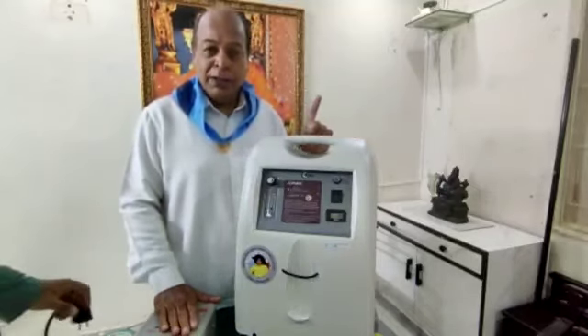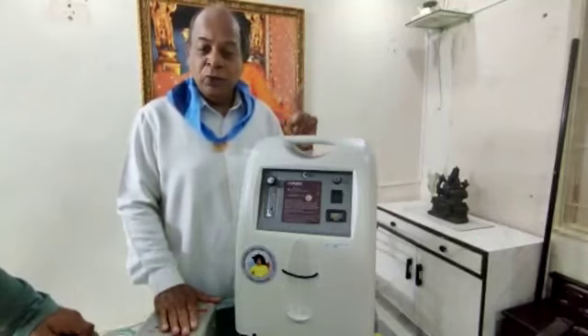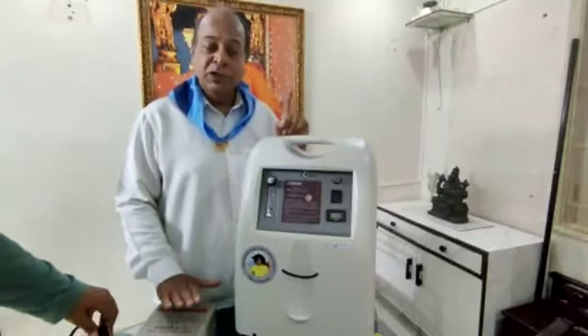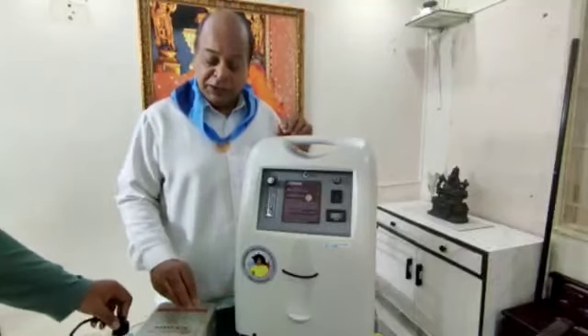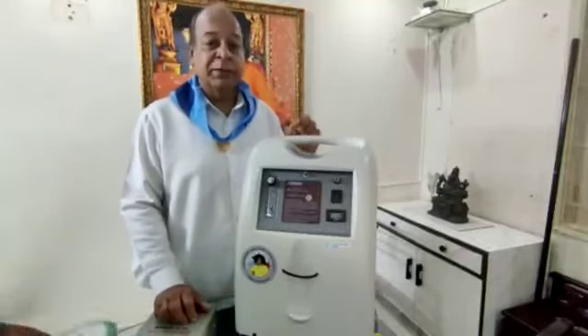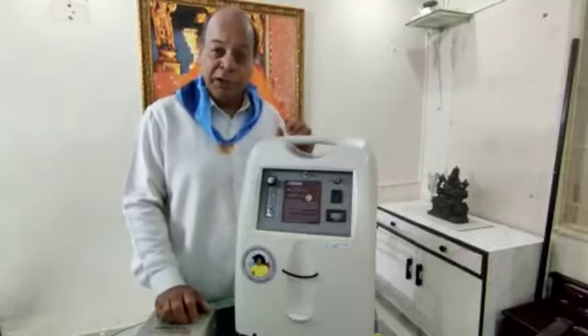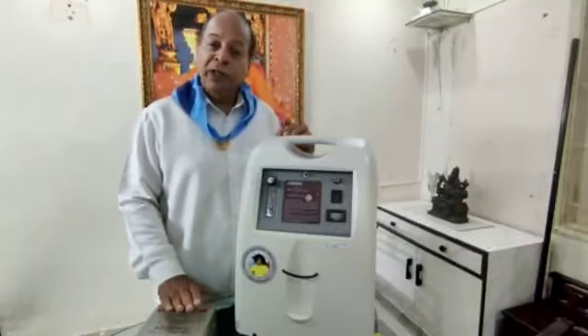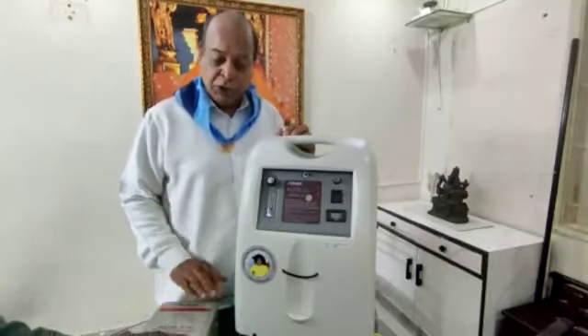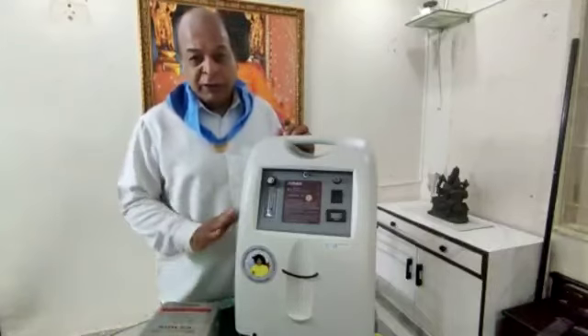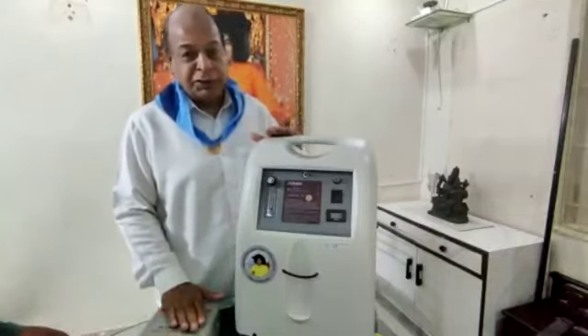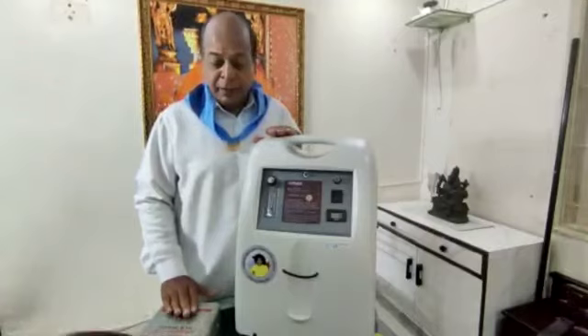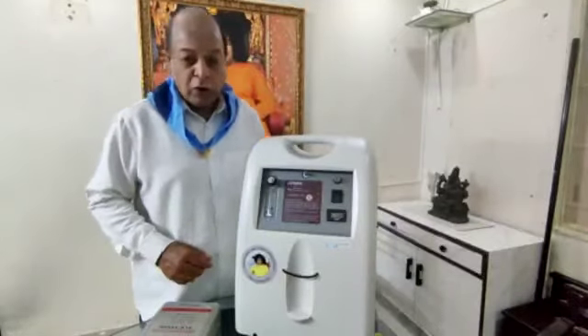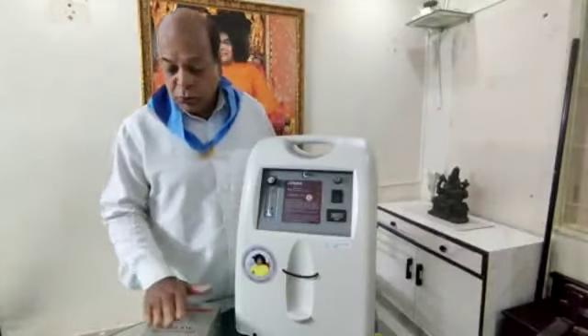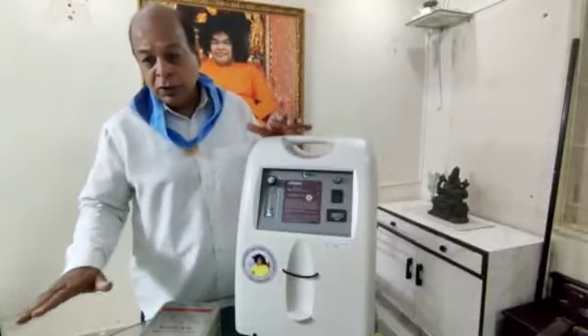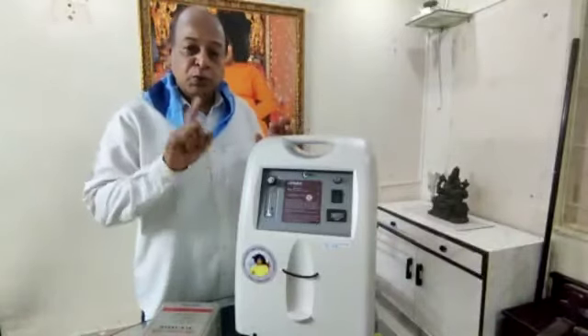So always buy the 220 volts one in India and don't buy a 110, because the oxygen concentrators which don't come with a step down transformer are not compatible in India. You'll have to find one with the required rating and wattage. So here is one concentrator with a step down transformer that has come with this machine. We plug the main cord of the oxygen concentrator into the transformer and the transformer into the plug point. Please do that first.